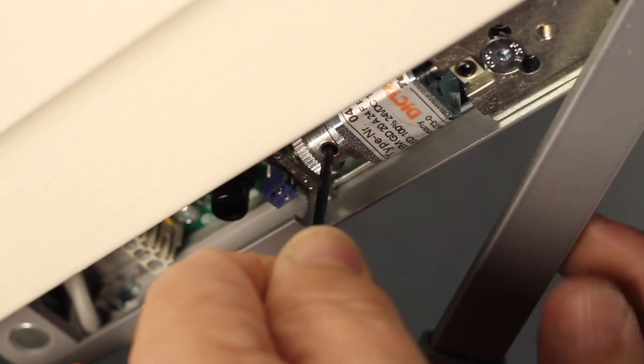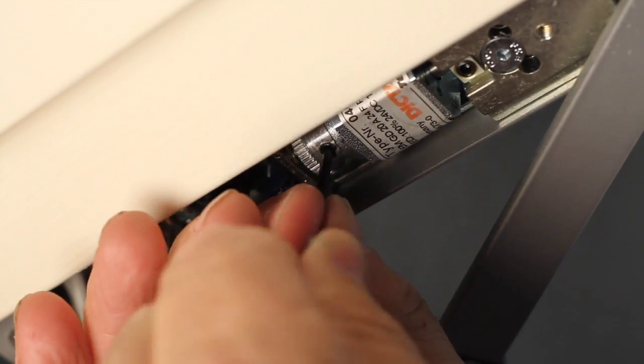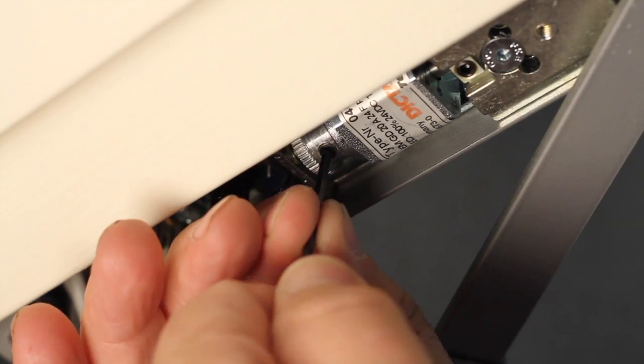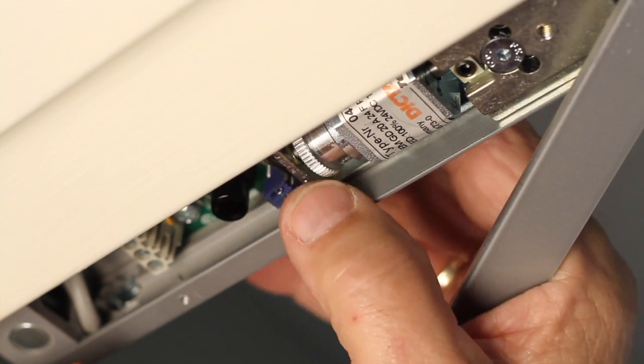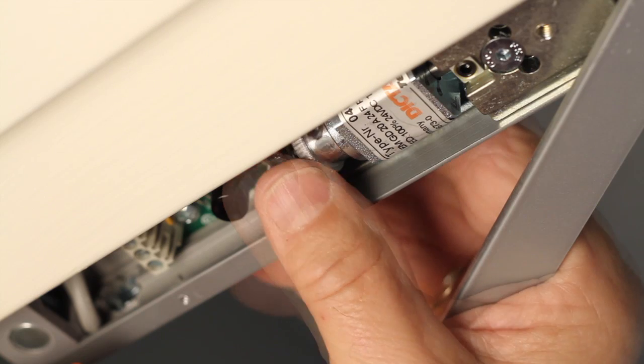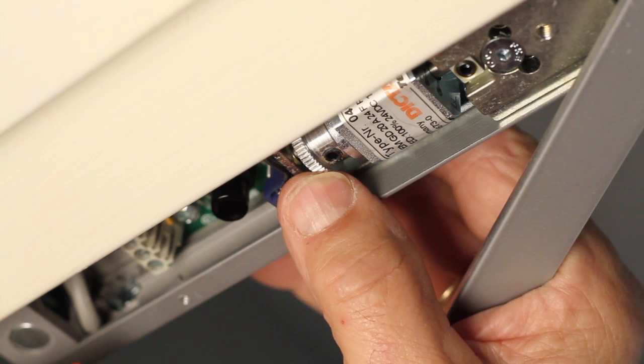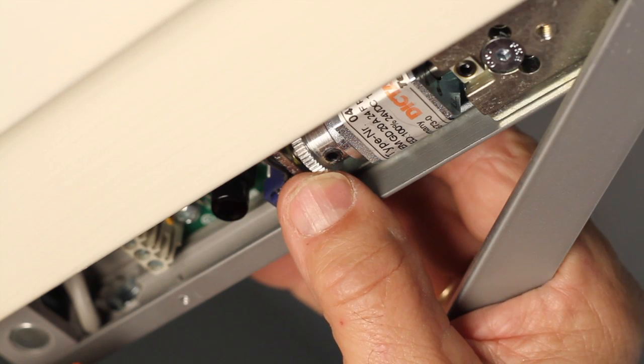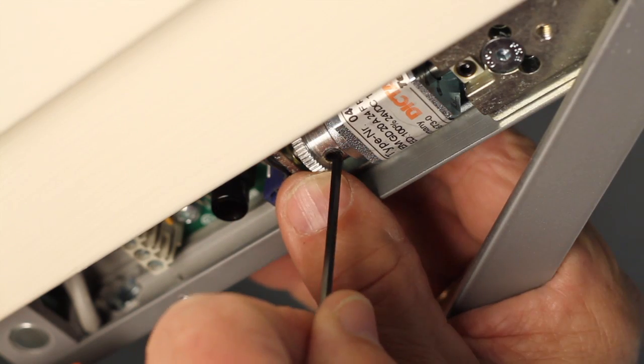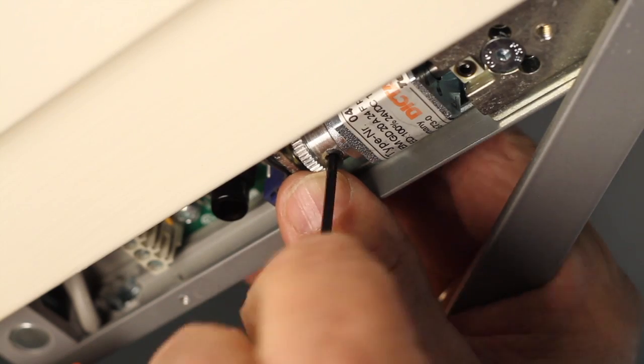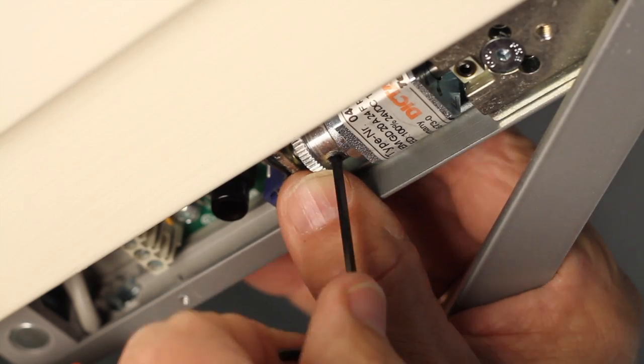Now loosen the 2.5 mm hex lock down screw as shown. Turn the knurled wheel clockwise to increase holding force and counterclockwise to decrease the holding force. When you have obtained the desired holding force, retighten the lock down screw.